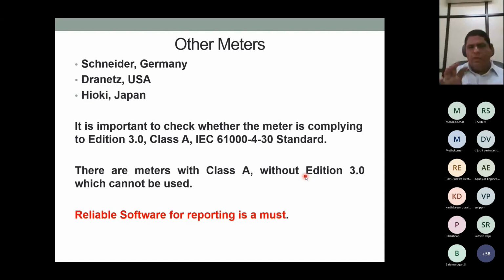It is very, very important. If a consumer wants to buy a meter, it is very important to check that it is edition 3. First it should be edition 3, then class A, then complying with these standards. Further to this, whatever the meter, there should be software which is reliable for reporting the IEC compliance.